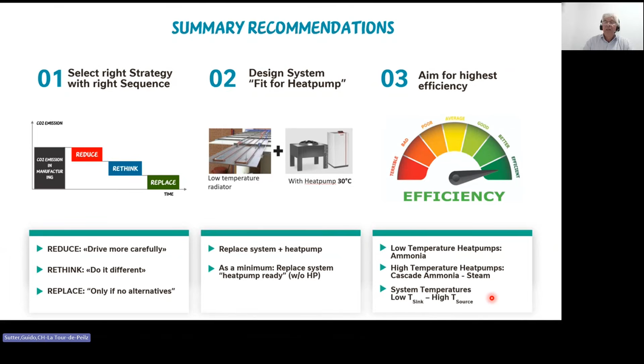Then our systems from now to be installed have to be at least fit for heat pump implementation. So if we do not want to invest in a heat pump right from the beginning because we don't trust it, make sure that the system as a minimum is heat pump ready: low sink temperatures, high source temperatures, not designed for steam, but designed for hot water, eventually to install the heat pump later on. And again, heat pump is key. System temperatures depend on the sink temperature and the source temperature. So design the systems already with adequate heat exchangers.